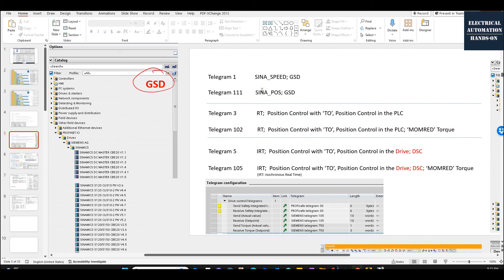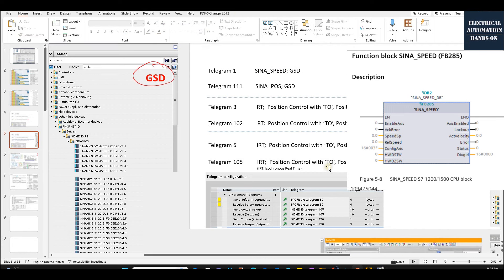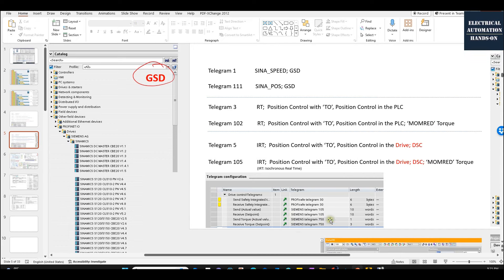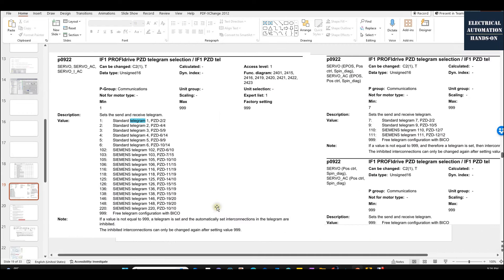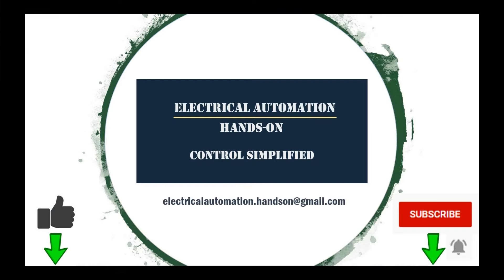For simple speed control — VFD or even servo speed control — you can use telegram 1 with SINA_SPEED and the provided function blocks. If your system has safety control, combine telegram 30 with telegram 1. For torque control, add telegram 750 for the speed control with torque reduction group. Definitely there are many other telegrams — for example parameter P0922 in the SINAMICS S120 shows all the telegrams it supports. That's the topic for today. Thank you for watching. If you like this video please give a thumbs up, subscribe, and hit the bell.